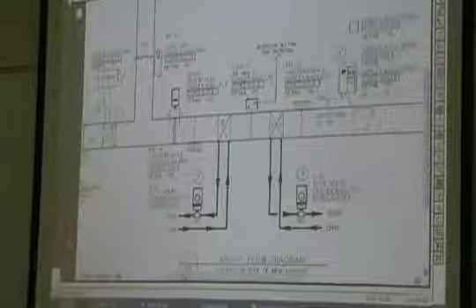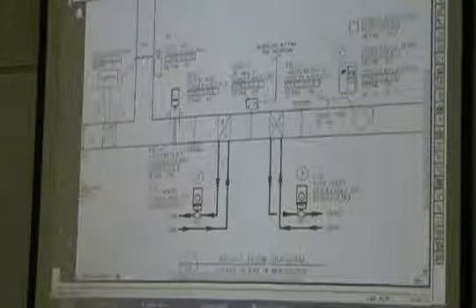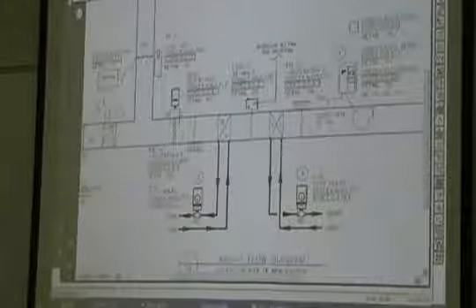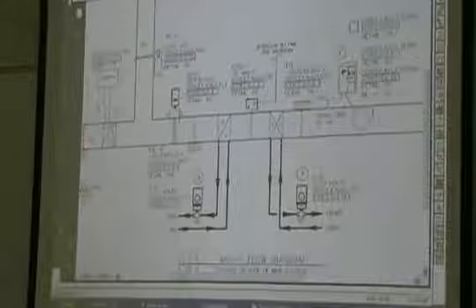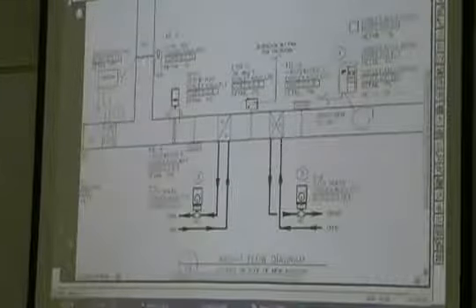Okay. Now, it keeps saying below to maintain some CFM above the minimum required. So we're always measuring our outdoor airflow, and we're not going to pinch the outdoor air damper down below that minimum airflow. Okay, so if we get down to where this is maintaining a minimum flow here and it's still too cold, that's when we'll start using the heating valve to bring that discharge air temperature back up. Any questions there?